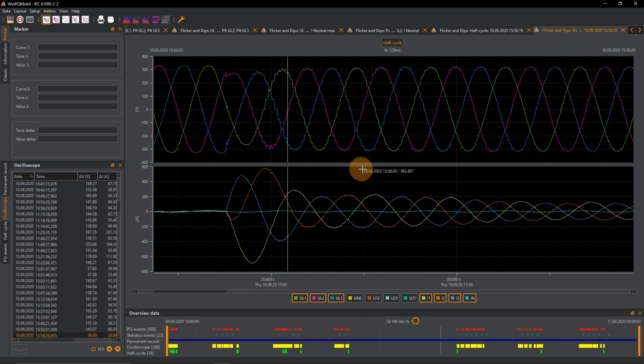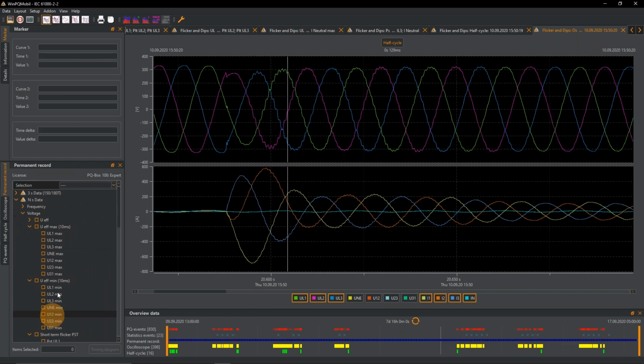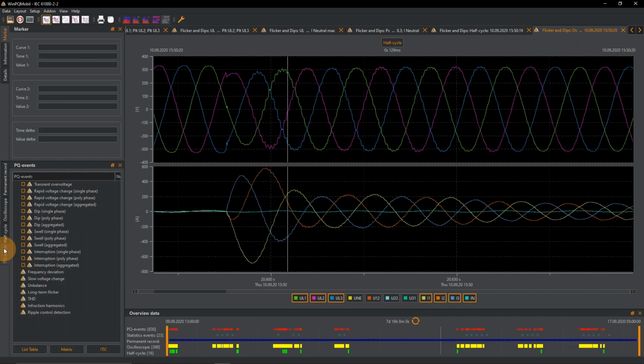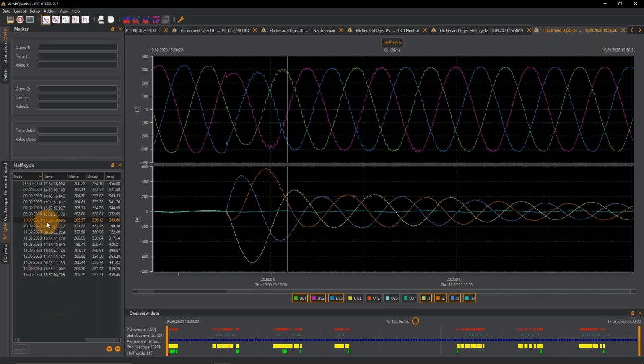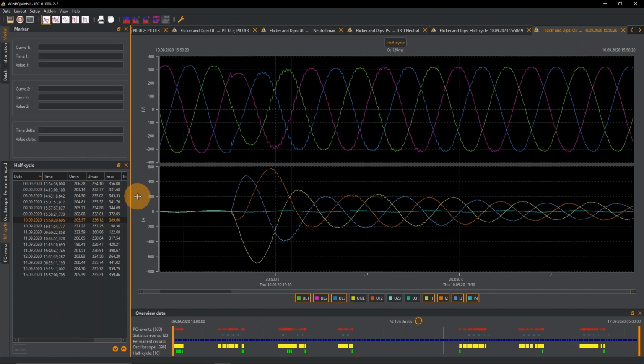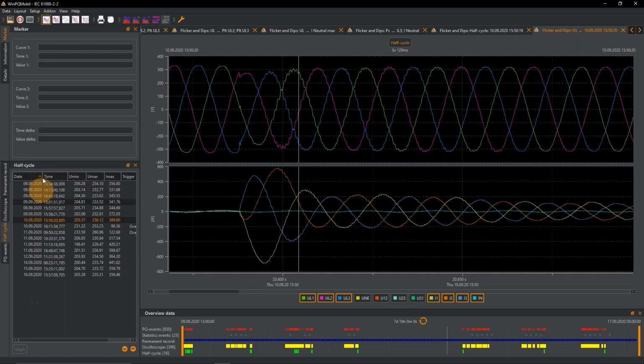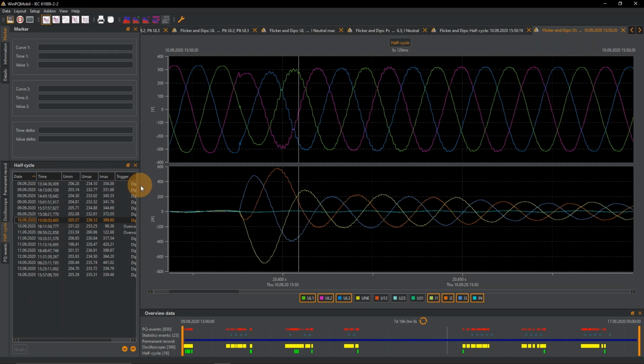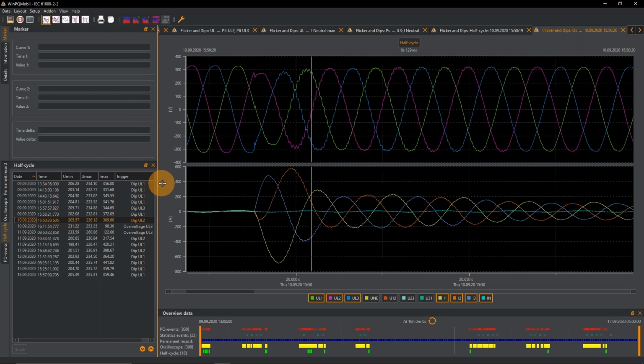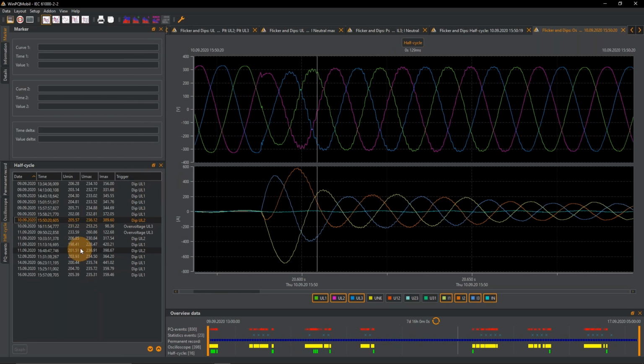The second way is I have a list on my left window. I have different tabs for permanent record. I used before oscilloscope, half cycle, and PQ events. And the bottom three ones are for our fault records. For example, I go to the half cycle, and here I can see a list of my half cycle events. I'll just display a little bit more. And now I'm able to filter. So I can click on the minimum voltage, and I can sort everything I want.